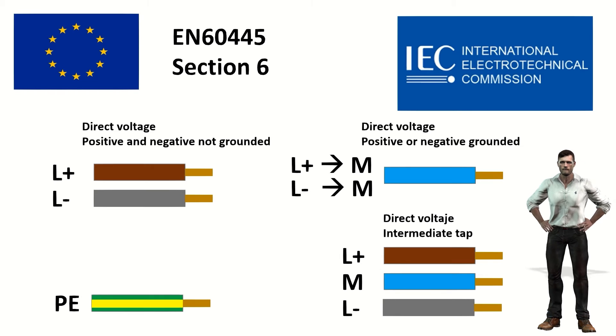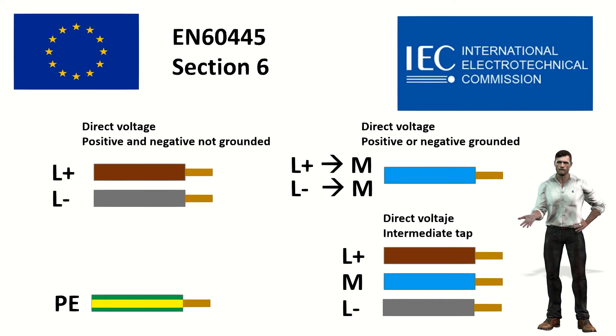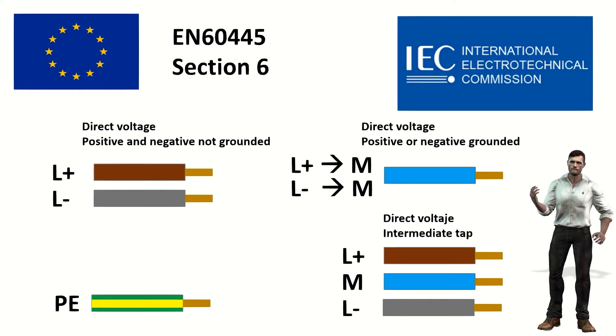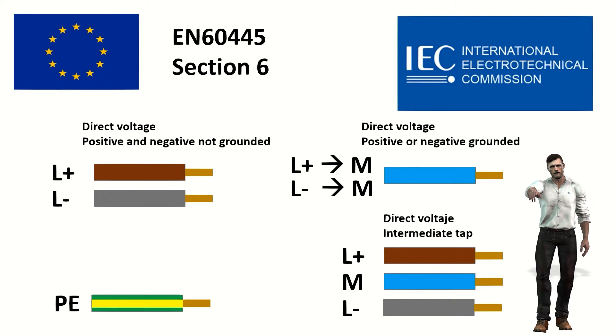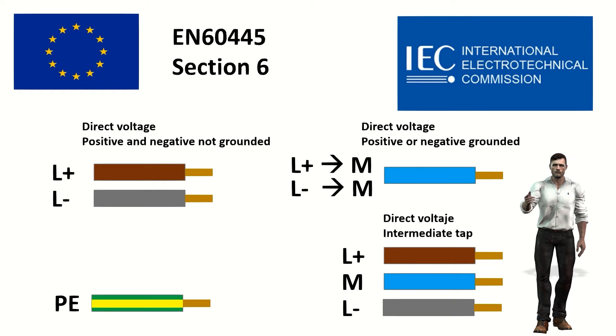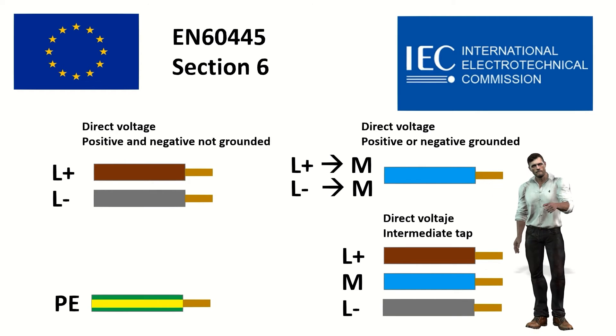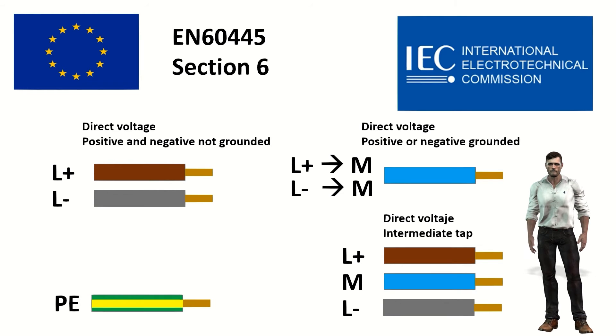For a DC installation with positive and negative not grounded: positive (L+) is brown, and negative (L-) is gray. In case the positive or negative is grounded, the blue color should be used and it would be labeled with the letter M. And if it is a system with an intermediate tap, the blue color is used for the cable of this intermediate outlet, labeled with the letter M. As in AC, the green color with the yellow line is used for the earth or protective conductor.